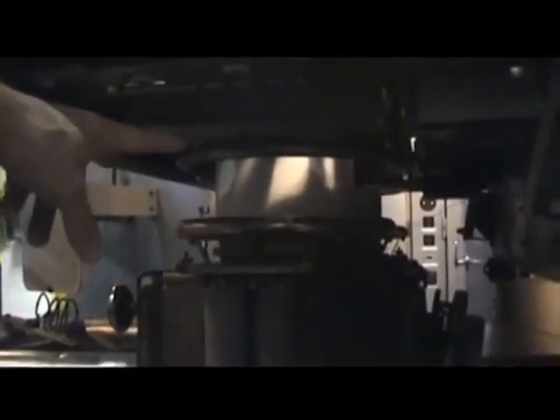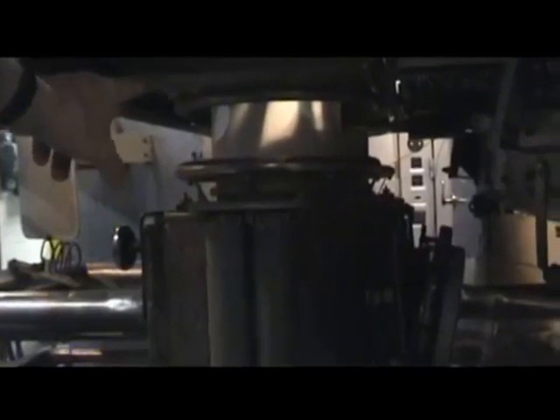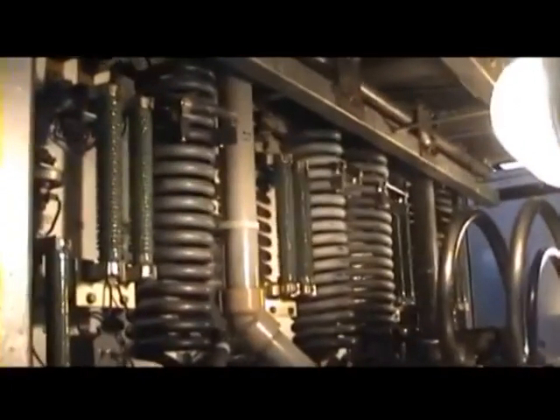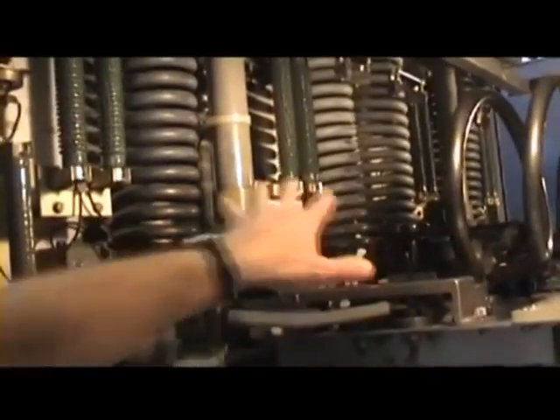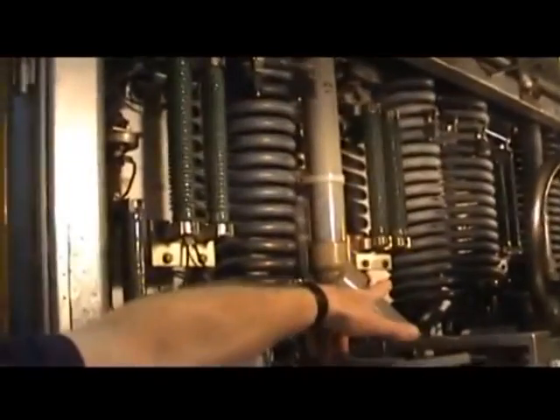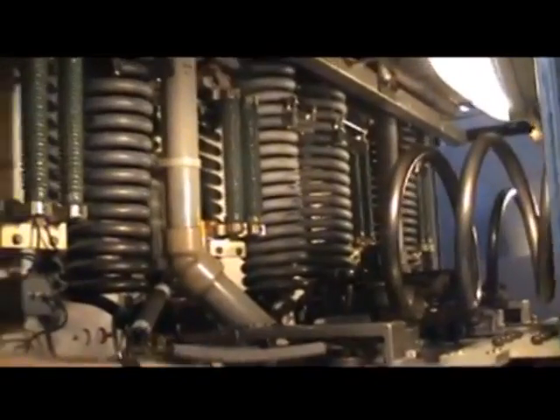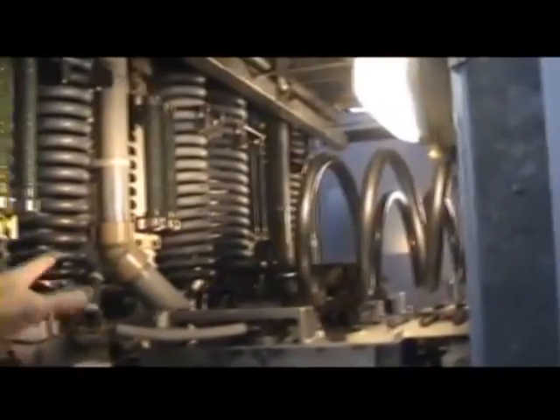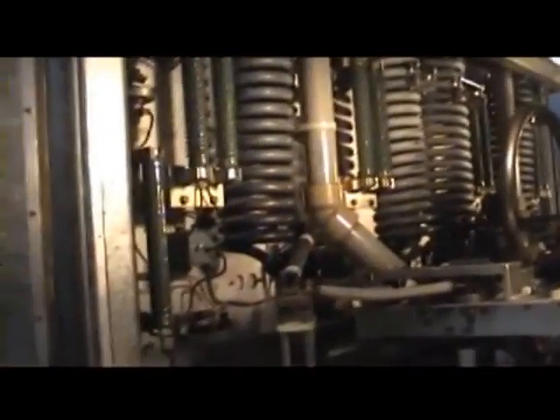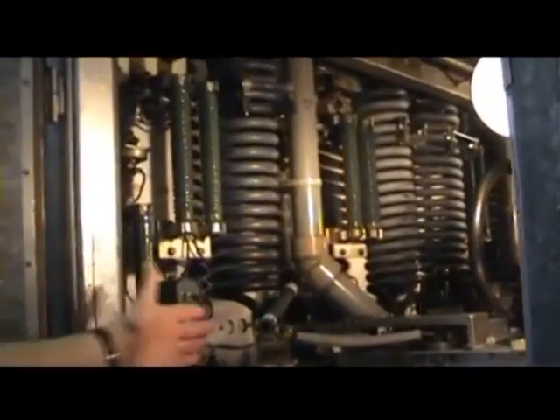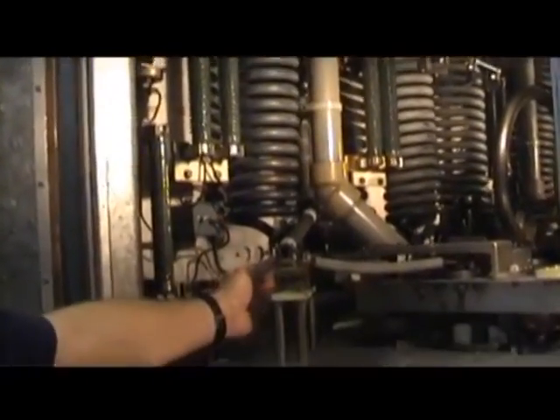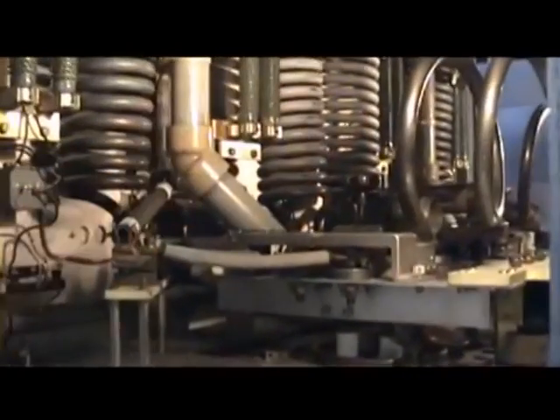And of course the ceramic on these output tubes is much larger than on the pen stage. The pen stage gives about 40 to 50 kilowatts output. These tubes give 125 kilowatts each. So it's a much larger tube. The filament supplies are much more comprehensive. So you've got 4 chokes for 2 tubes. Here's one of them, the one there. Within the tube are 2 separate filaments, 325 amps at 9 volts on each one. And there's the connections to one set of the filaments, and off it goes into the valve.